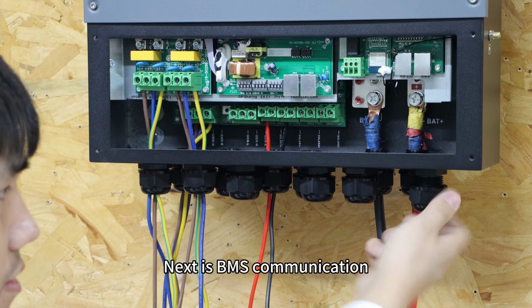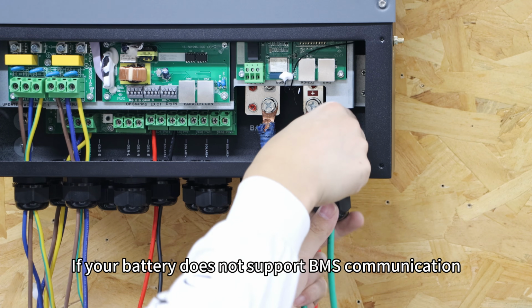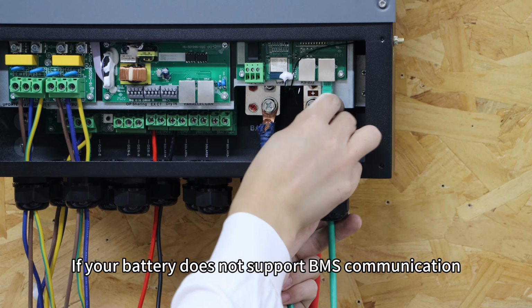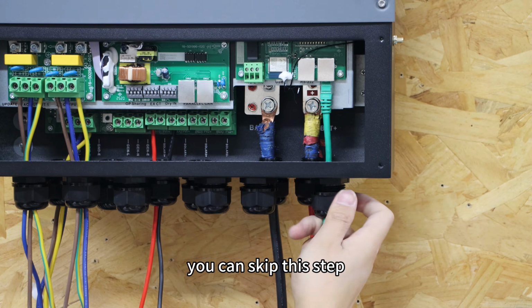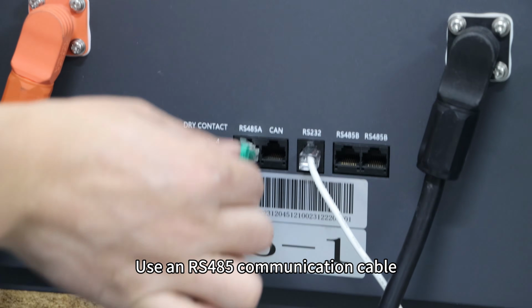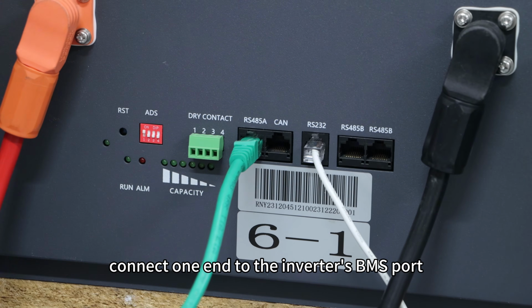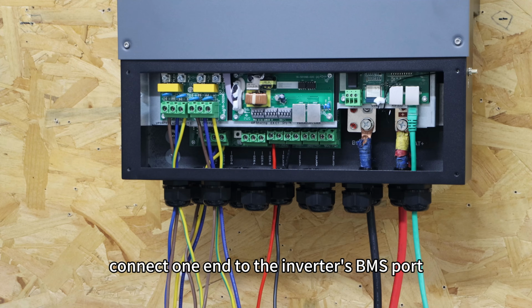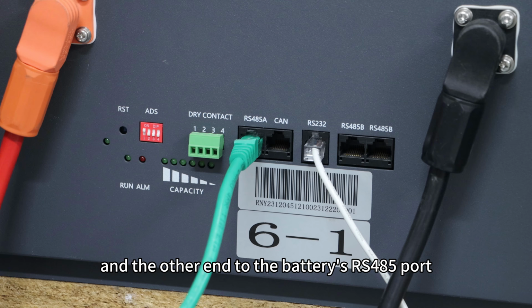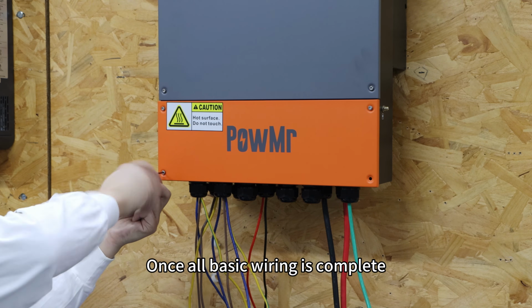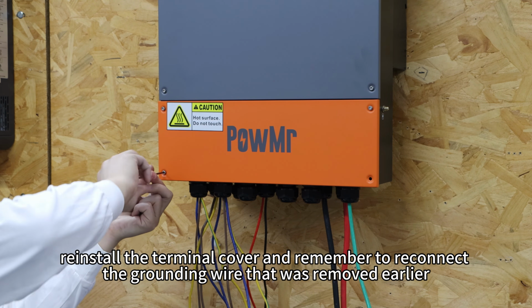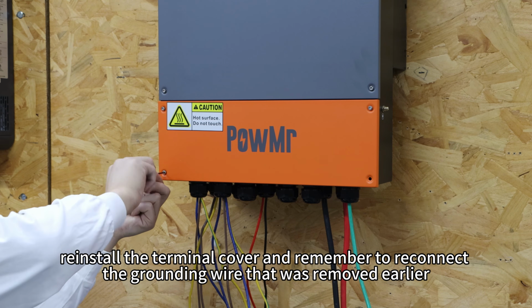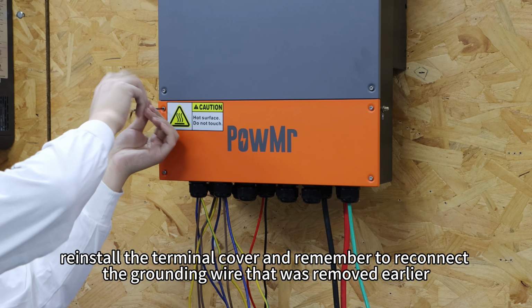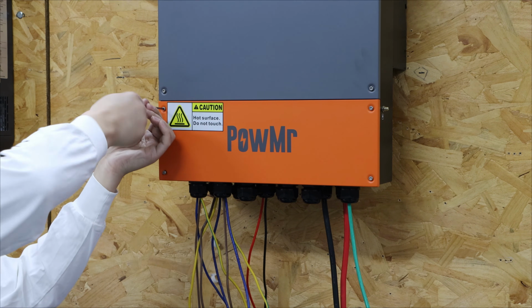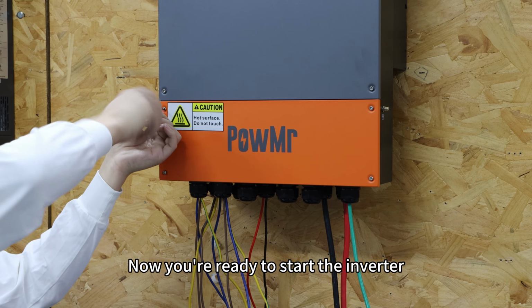Next is BMS communication. If your battery does not support BMS communication, you can skip this step. Use an RS-485 communication cable. Connect one end to the inverter's BMS port and the other end to the battery's RS-485 port. Once all basic wiring is complete, reinstall the terminal cover and remember to reconnect the grounding wire that was removed earlier. Now you are ready to start the inverter.